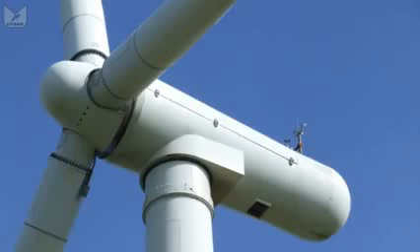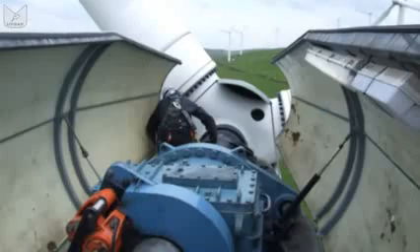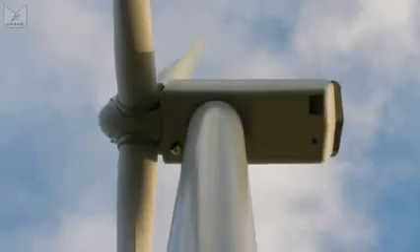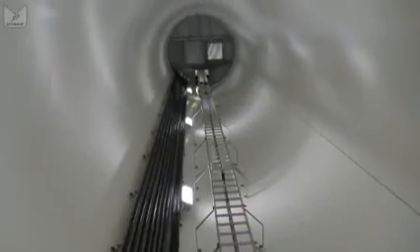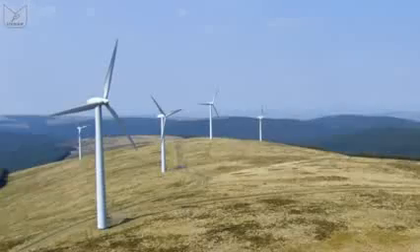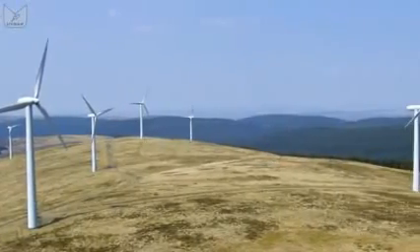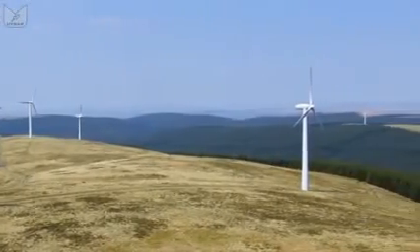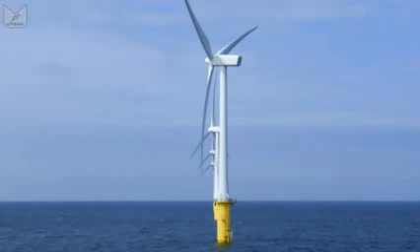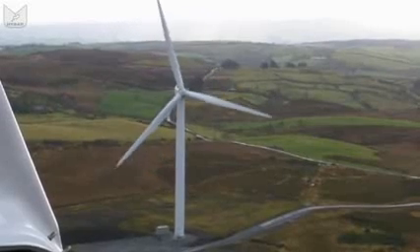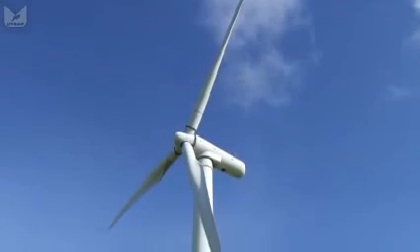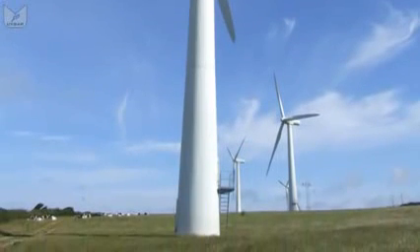And in this nacelle we have the generator, often a gearbox, and occasionally a high-voltage transformer, and the whole thing sits on top of a tower, which is mostly there to keep the blades from digging a hole. We tend to class turbines by their power output, and hence their physical size. Wind farms might use many sub-megawatt turbines, each producing 400-600 kilowatts, or a few multi-megawatt turbines, producing maybe up to 3 megawatts per unit. Apart from physical scale, they are arranged a bit differently, so let's start by looking at a typical sub-megawatt model.